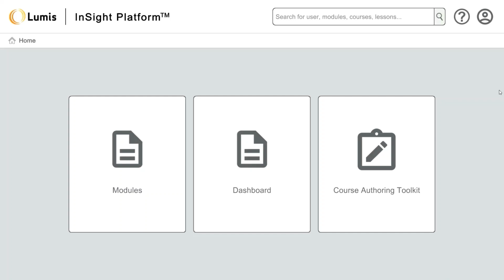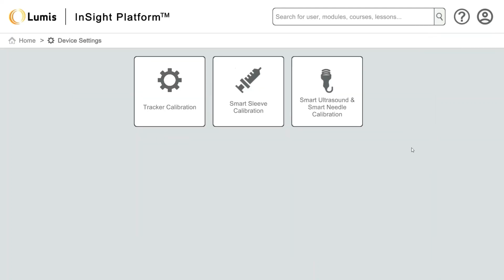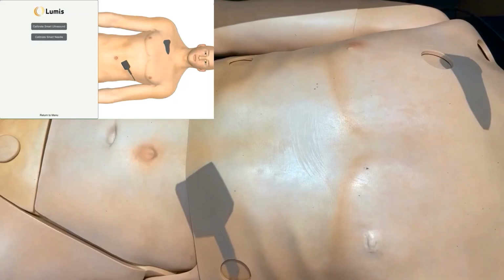Both the Smart Ultrasound probe and Smart Needle require rotational calibration to ensure that their orientation is accurately detected during use. To calibrate them, open Device Settings by pressing the icon in the top right corner and clicking Device Settings. Then, open Smart Ultrasound and Smart Needle calibration. Here, you can see the virtual ultrasound probe and virtual needle projected onto the body. In the upper left corner, you can see a picture-in-picture view of the tablet display.